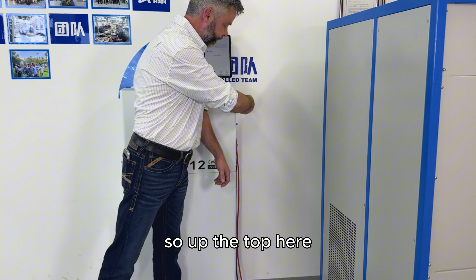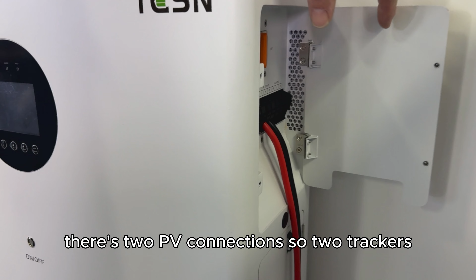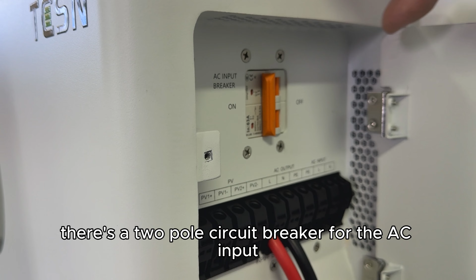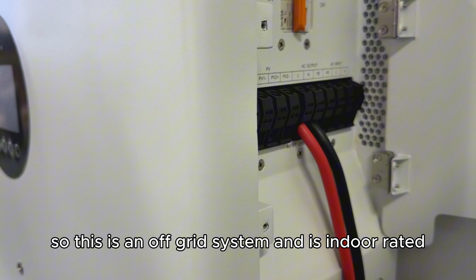On the side here, we've got all the connections. So up the top here, there's two PV connections, so two trackers, MPPT1, MPPT2. There's a 2-pole circuit breaker for the AC input, and then there's the AC output connection and the AC input connection, being a generator in this case. So this is an off-grid system and is indoor rated, so it's not suitable for outdoor use.